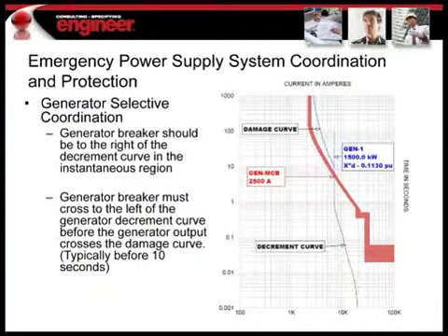So how do we coordinate with this system, with this damage and decrement curve? What we want to do is set a breaker, or possibly in some situations you can use the generator relay control that is inside the generator controllers. Some manufacturers do make very sophisticated relay modules inside the controllers that would do this function, and they're actually quite good at it as well. But as far as our breakers are concerned, the breaker that protects the generator, we want to allow the fault to happen for a certain amount of time, and then make sure that our breaker crosses the decrement curve, so it's on the left side of the decrement curve at some point before you get to the damage curve.